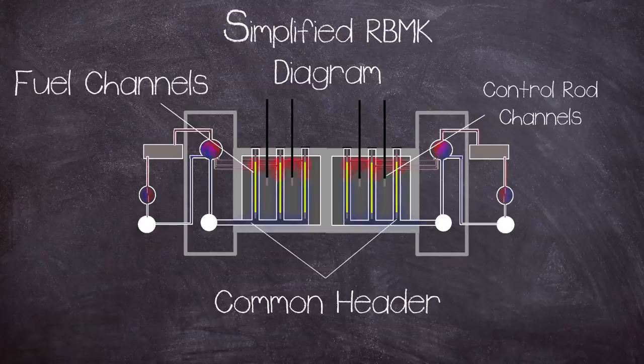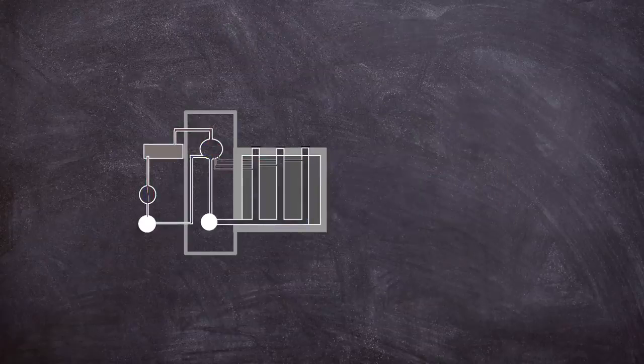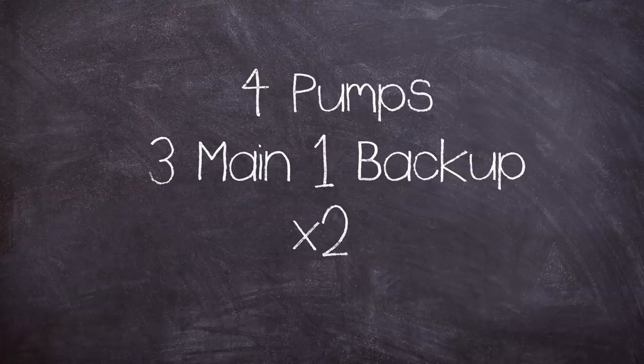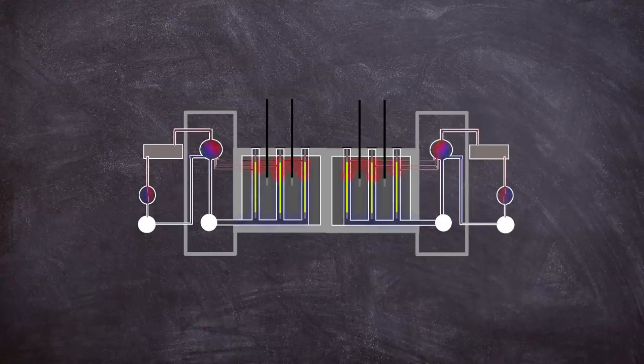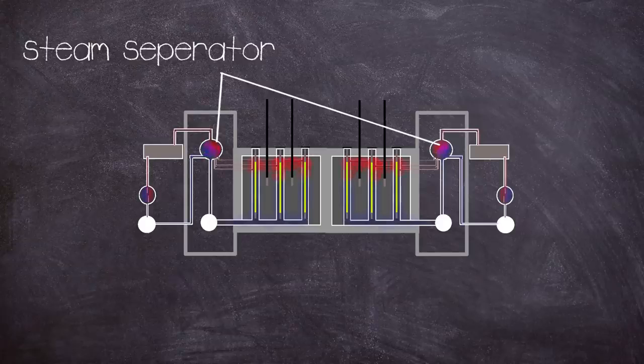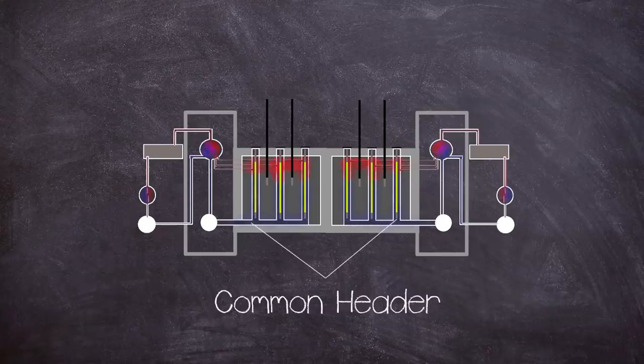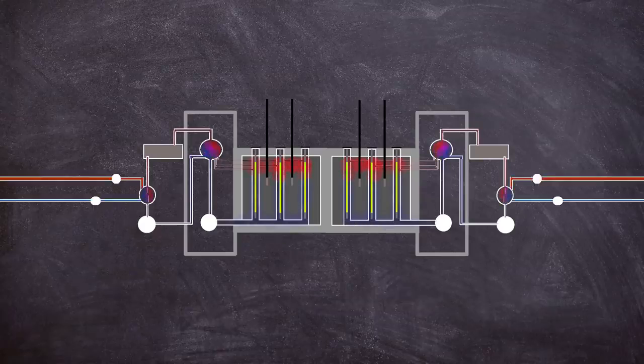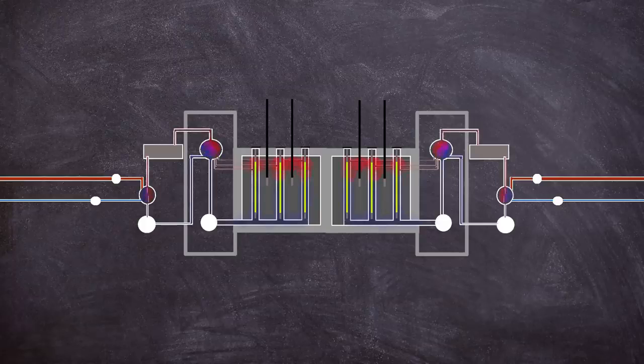The primary cooling of the reactor was via two separate cooling circuits, one for each half of the core. Meaning everything was doubled up leading to four main circulating pumps, three operating and one standby per loop. As the coolant boils it exits the top of the core and is passed through a water steam separator which takes the steam to high then low pressure turbines which generate electricity. The steam is then passed through a condenser that turns it back into water to be pumped back into the core completing the primary cooling circuit. The condenser is cooled by using a separate secondary water cooling circuit meaning the primary cooling circuit is self-contained.